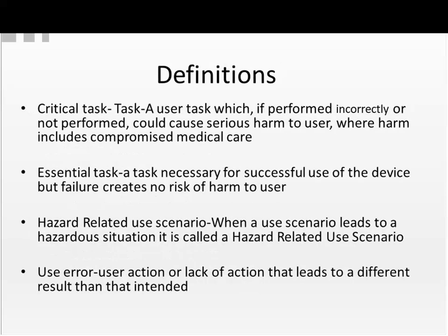Critical task. A user task which, if performed incorrectly or not performed, could cause serious harm to user, where the harm includes compromised medical care. Essential task is a task necessary for successful use of the device, but failure creates no risk of harm to user.